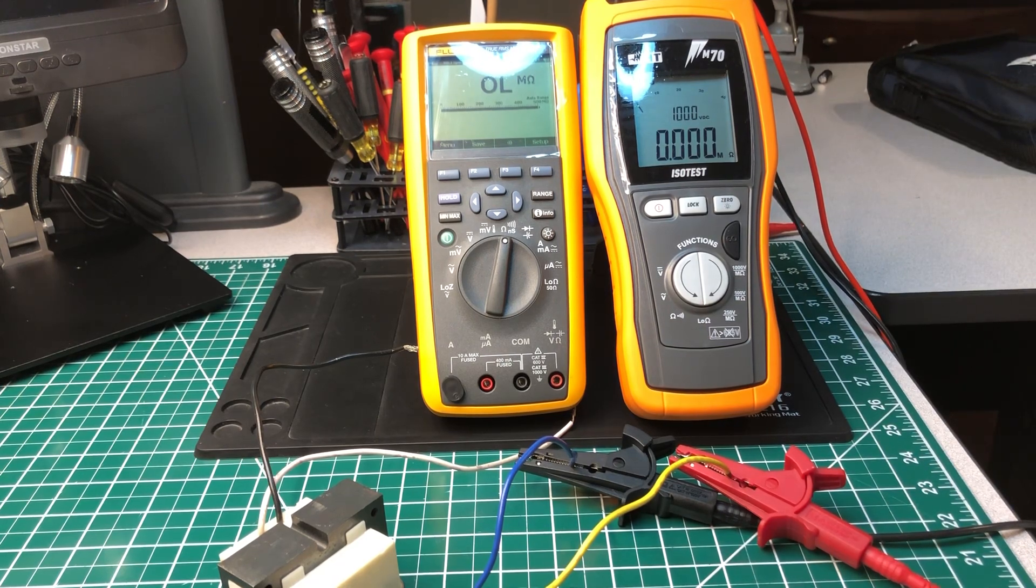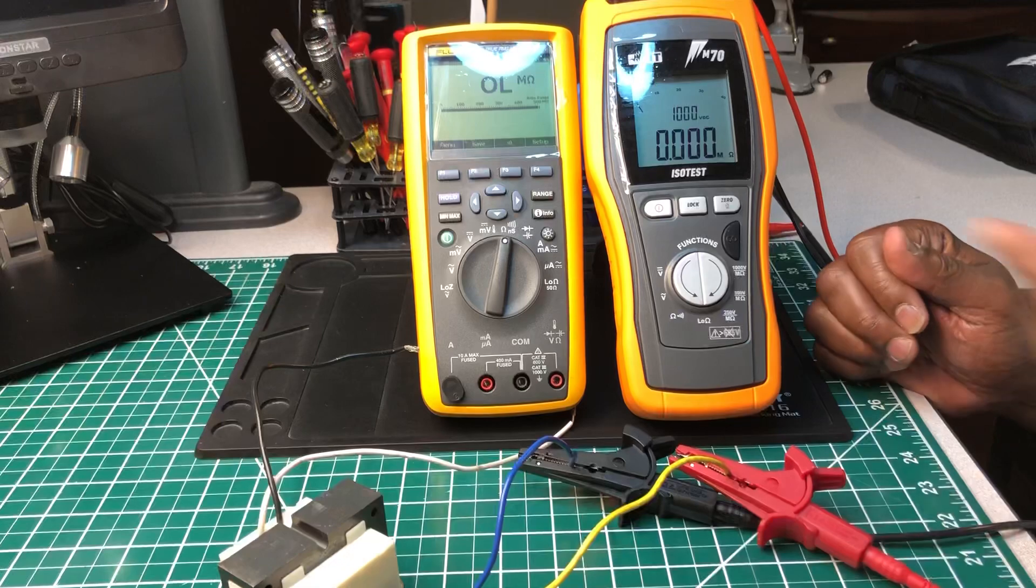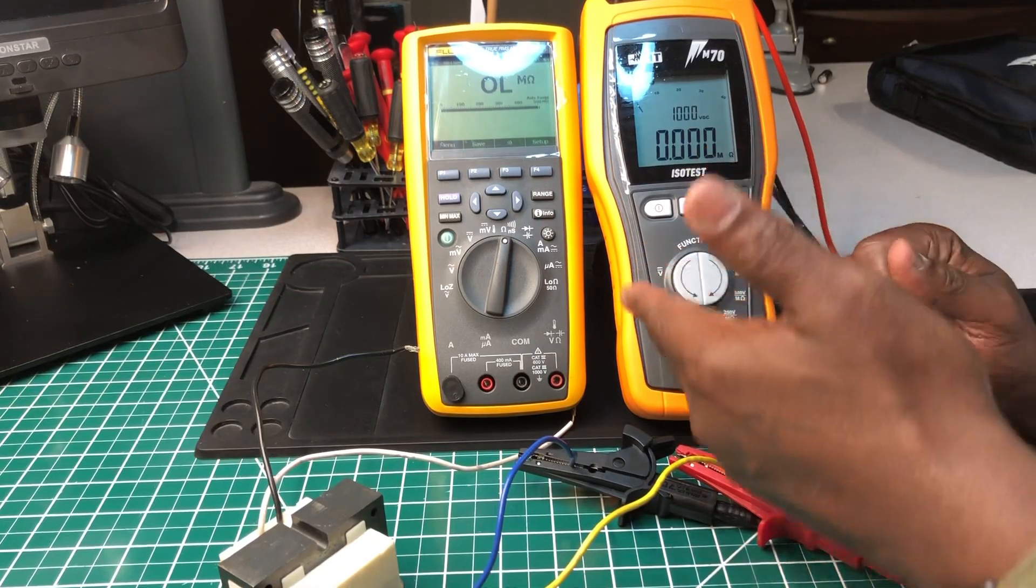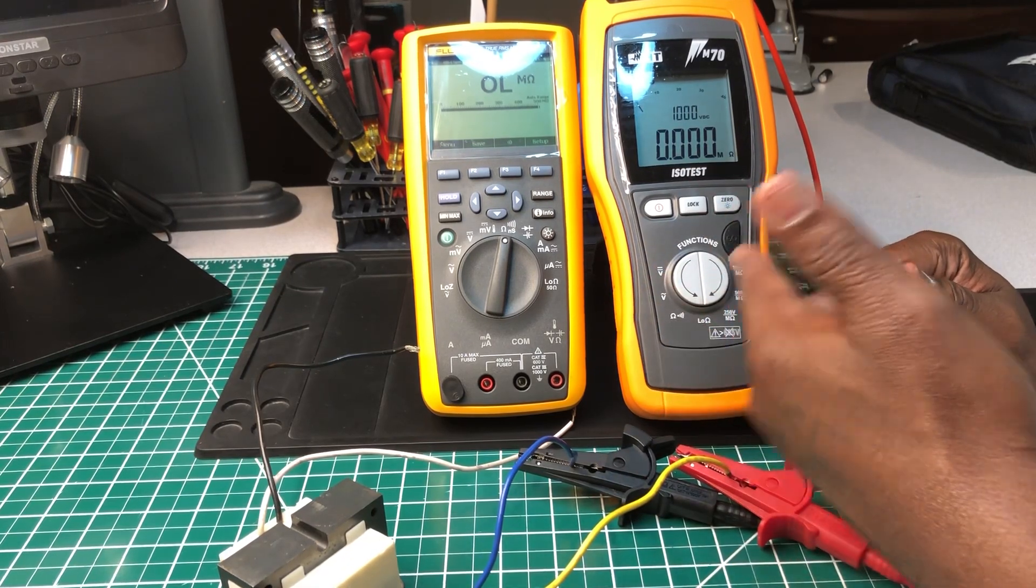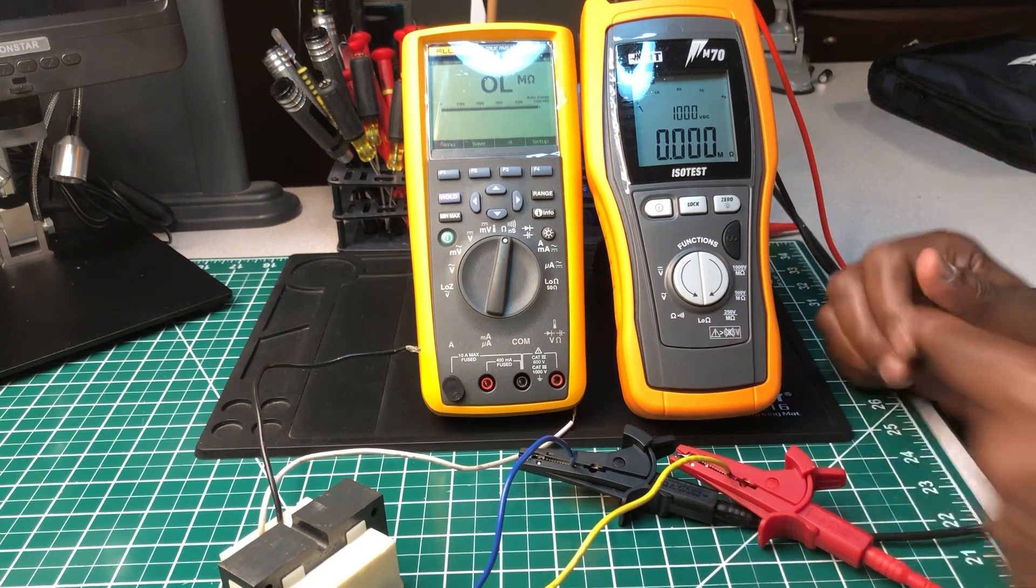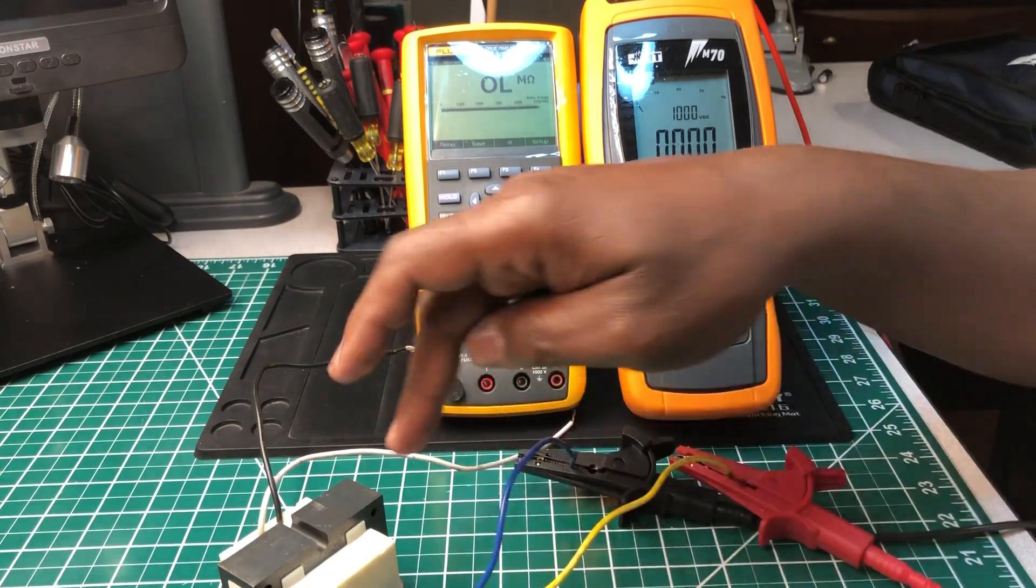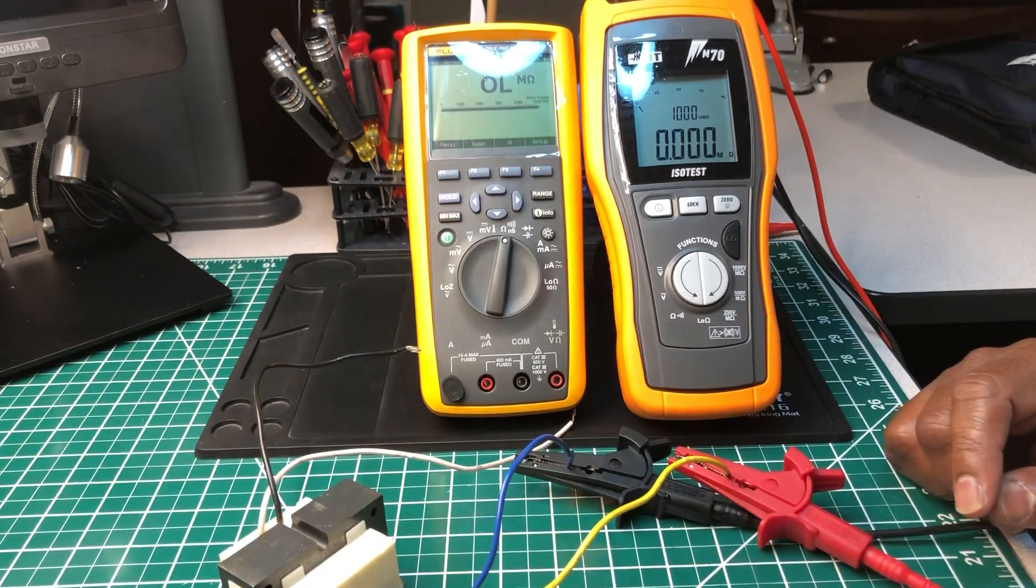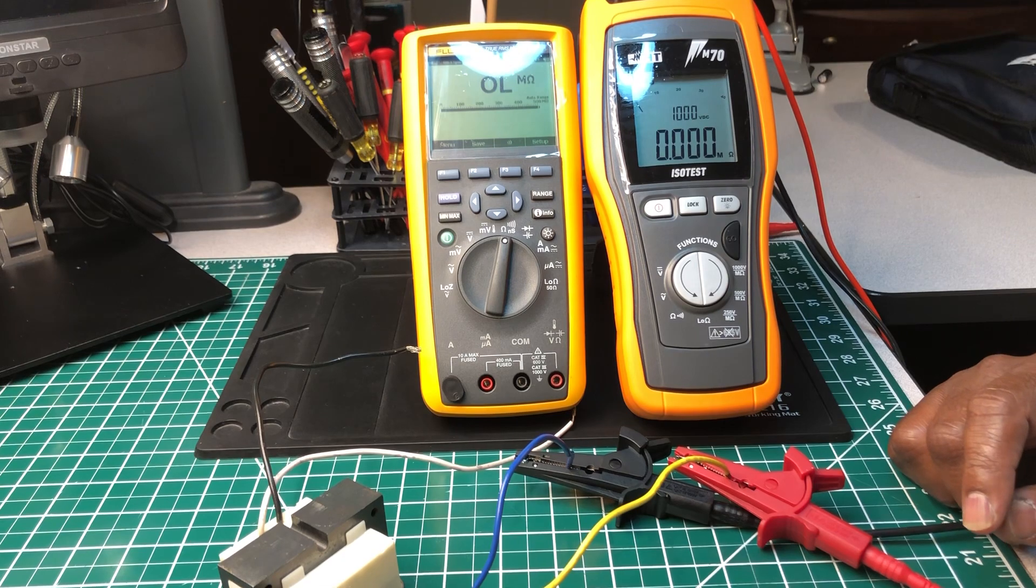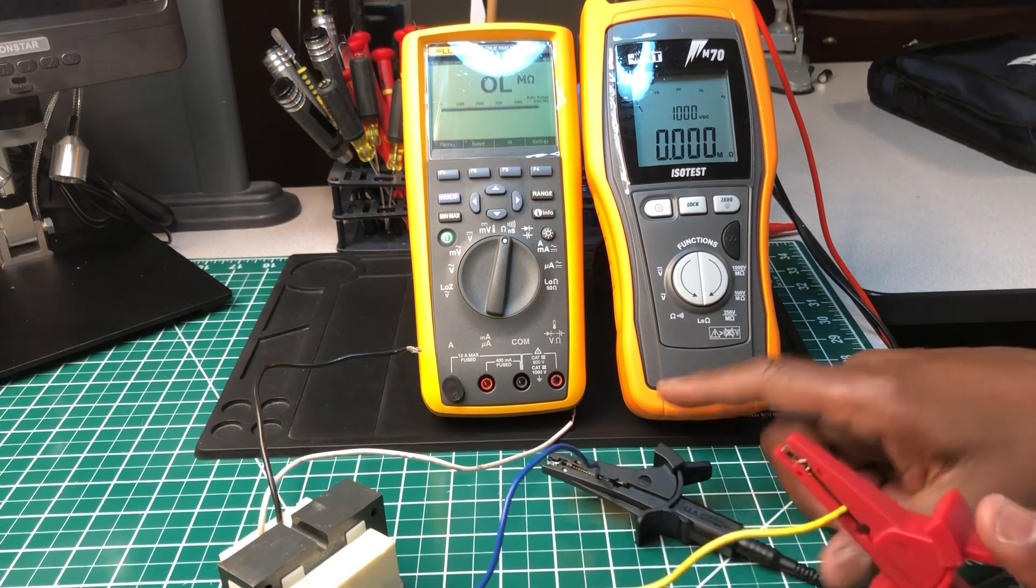Here we go. No resistance. The windings or the wires inside this transformer are good - it's a perfectly good transformer. Which one would I rather use out of the two? I would use this insulation tester because I can apply more voltage using this to check the winding and determine if this transformer is really good or bad.